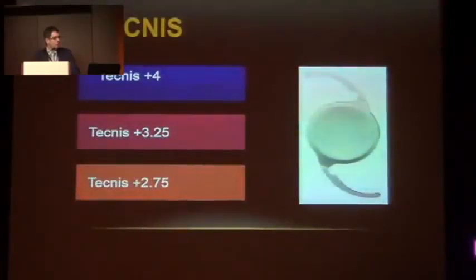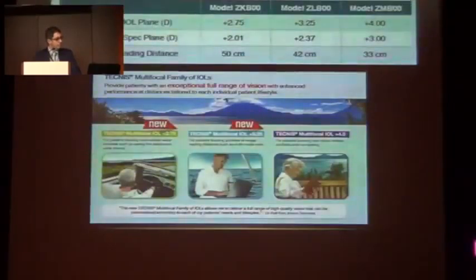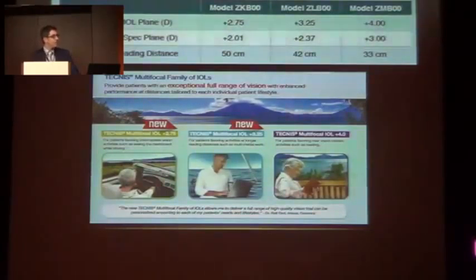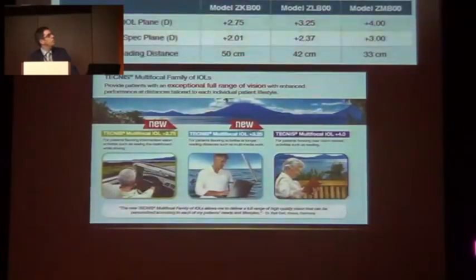We have three different addition options: plus 4, plus 3.25, and plus 2.75. These models are called ZKB00, with a theoretical medium distance of 50 centimeters; the ZLB, with a theoretical medium distance of 42 centimeters; and the classic ZMB, to read at 33 centimeters.